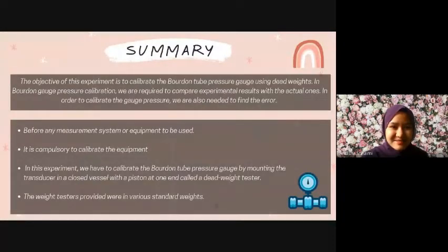The objective of this experiment is to calibrate the Bourdon Tube Pressure Gauge using dead weights. In Bourdon gauge pressure calibration, we are required to compare experimental results with the actual ones. In order to calibrate the gauge pressure, we also need to find the error. Bourdon tube is one of the equipment to measure pressure. Before any measurement system or equipment is used, it is compulsory to calibrate the equipment, so that the equipment can be just as accurate as a working standard. To calibrate a measurement system, we have to compare its theoretical pressure with measured pressure.